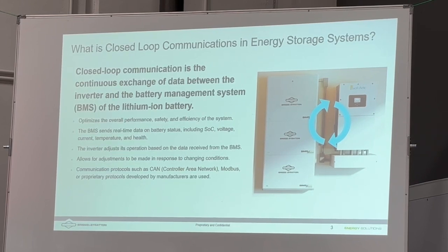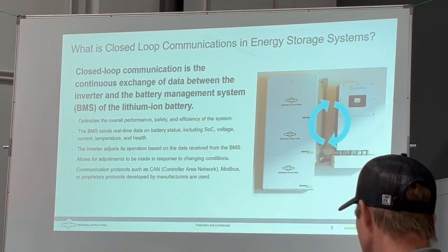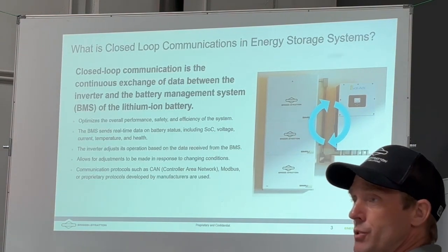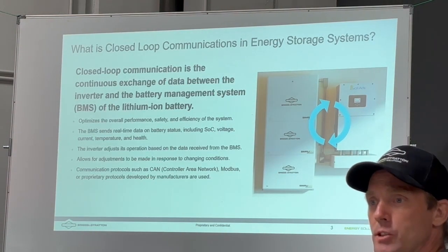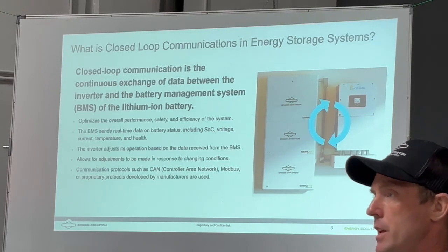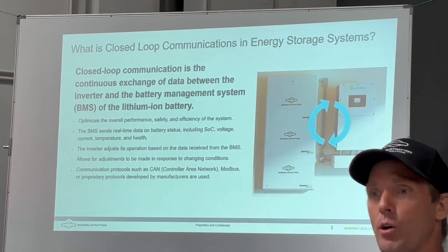The batteries will automatically adjust the settings in the Sol-Ark based on battery conditions. If the battery is really cold, it might slow the charging rate down. If the battery is getting full, it tells the Sol-Ark its current status, and the Sol-Ark can respond to that information. Each battery module has multiple temperature sensors throughout, communicating temperature, state of charge, and state of health with the Sol-Ark.